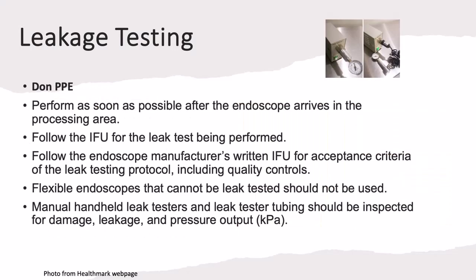When you do leak testing, you want to put on your PPE and perform the leak testing as soon as possible after the endoscope arrives in the processing area. You have to follow the instructions for use for the specific leak test that's being performed. But you also have to follow the endoscope manufacturer's written instructions for their criteria of the leak testing protocol, including quality controls you should be doing. Flexible endoscopes that cannot be leak tested should not be used. And manual handheld leak testers and leak tester tubing should be inspected for damage, leakage, and pressure output.